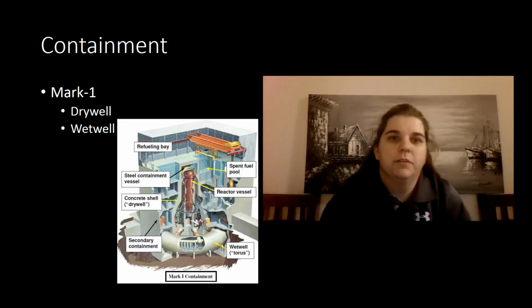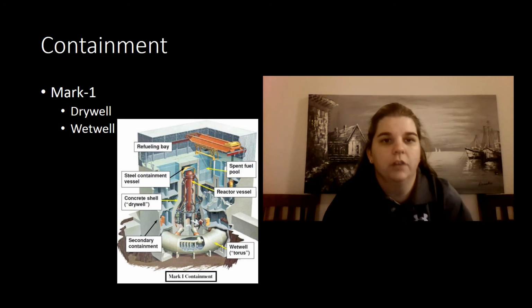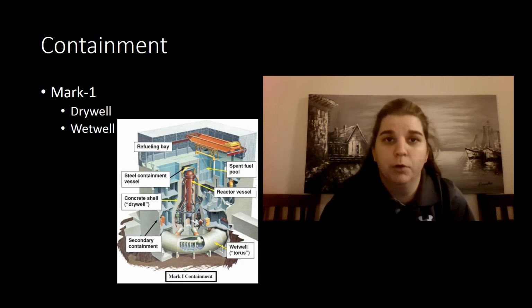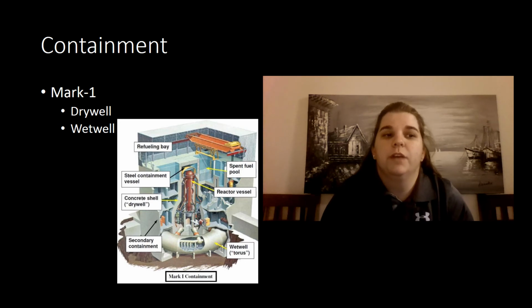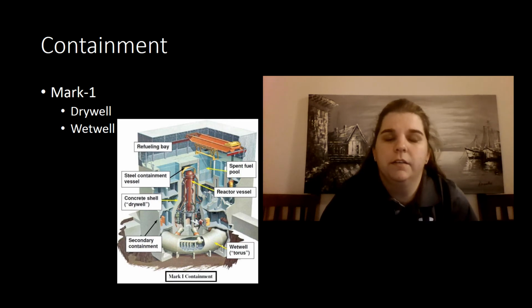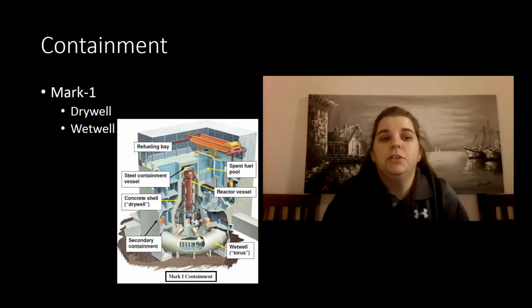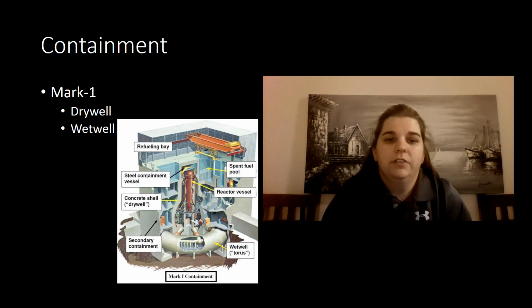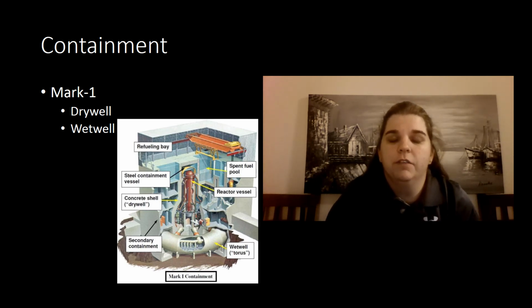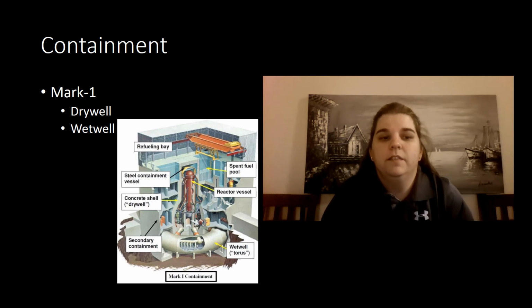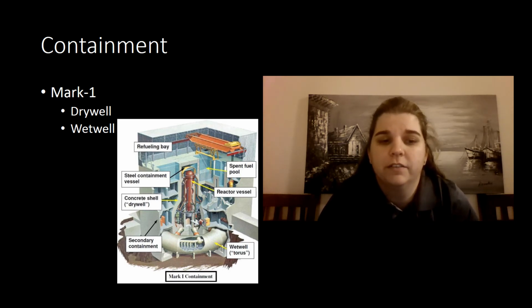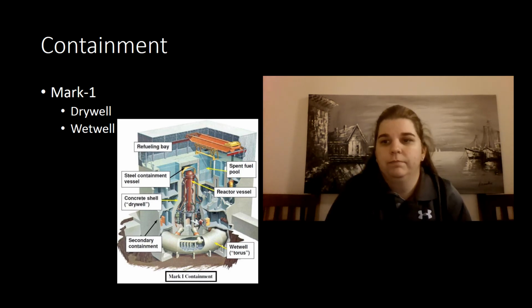The boiling water reactor Mark I containment is a dry well made of 30mm steel that is reinforced with a concrete shell. The shape of this containment is bulb-shaped. This dry well contains the reactor pressure vessel. Under the dry well containment is a torus-shaped wet well that contains a suppression pool. The dry well and wet well are connected by a system of vents. The function of the primary containment is to contain the energy in the event of a loss of coolant casualty. This containment also protects the reactor from any outside assault.